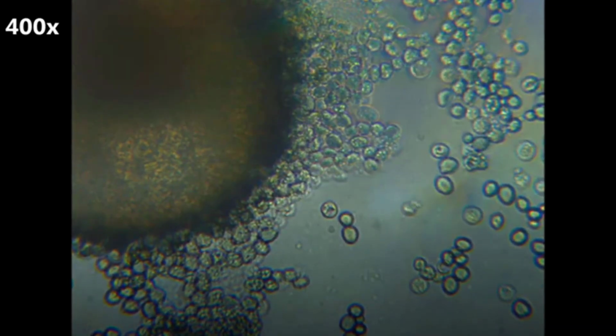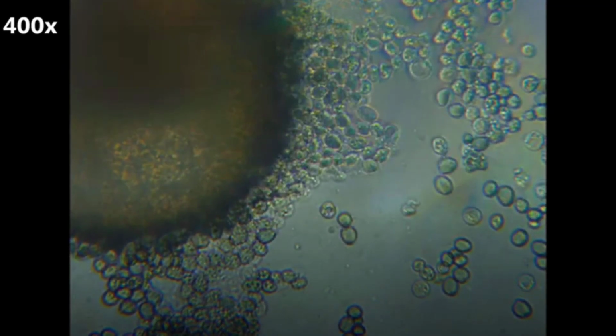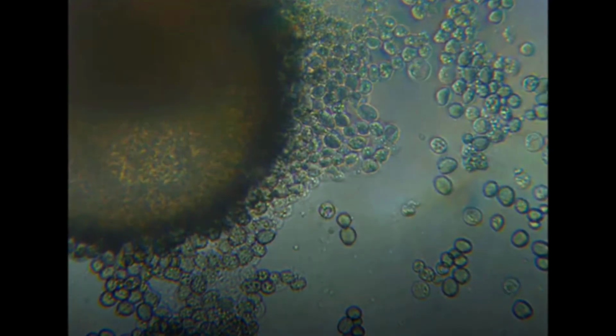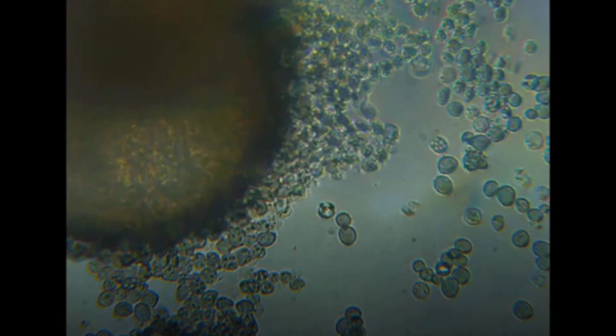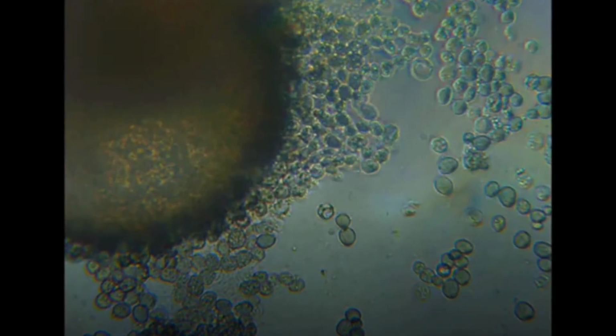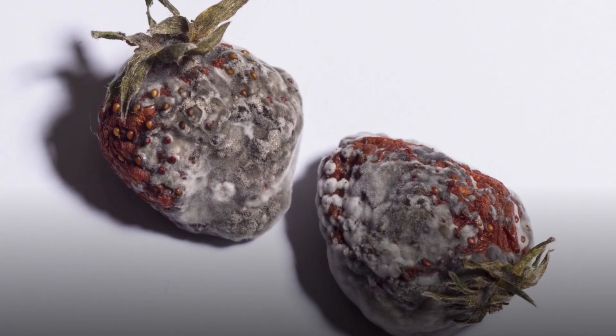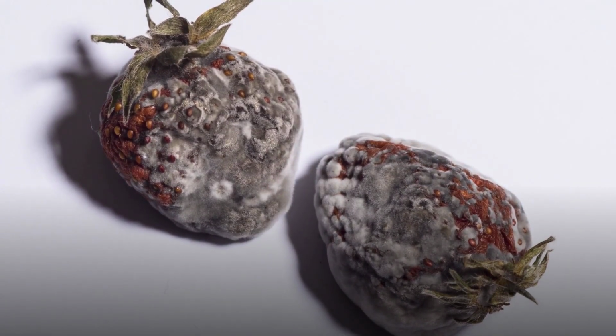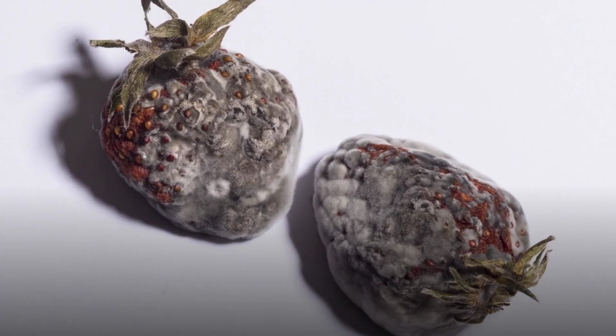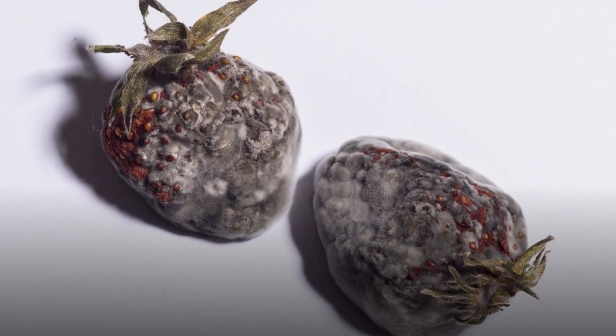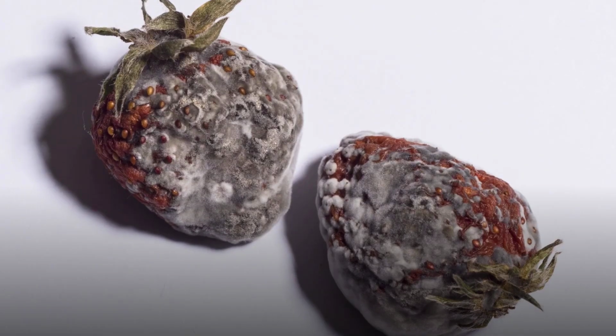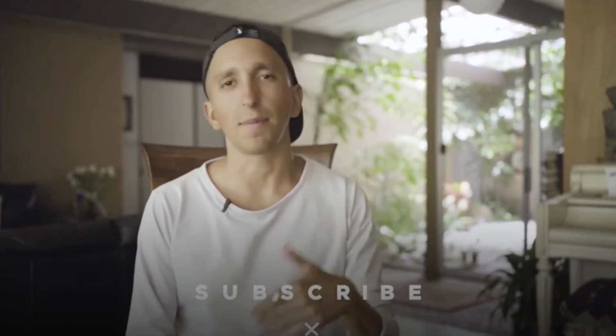A common concern with earth tunnels relates to indoor air quality, specifically the potential for mold growth or radon gas infiltration. However, these issues are largely preventable with proper design and installation. Using smooth, impermeable pipes, ensuring adequate drainage for condensation, and maintaining sufficient airflow are crucial. Additionally, a radon mitigation system can be integrated if the local geology presents a risk. With careful planning, an earth tunnel can deliver fresh, cool air without compromising health or comfort, debunking myths about inherent dangers.